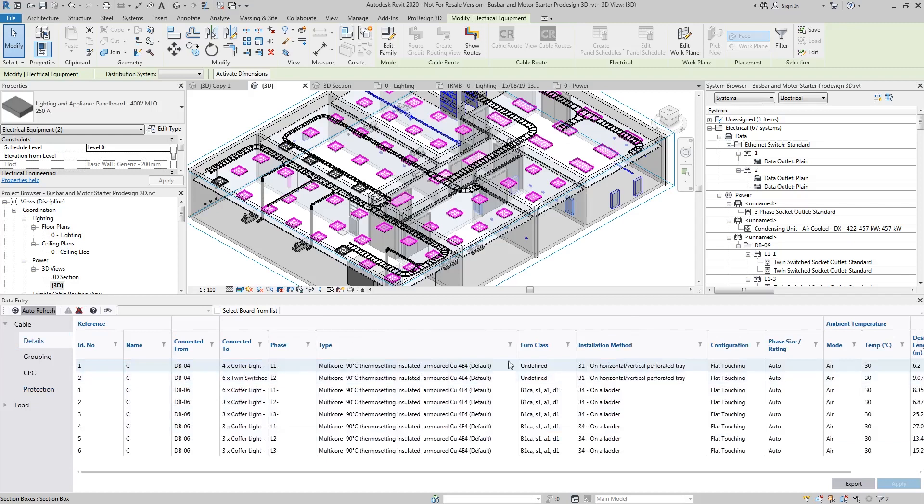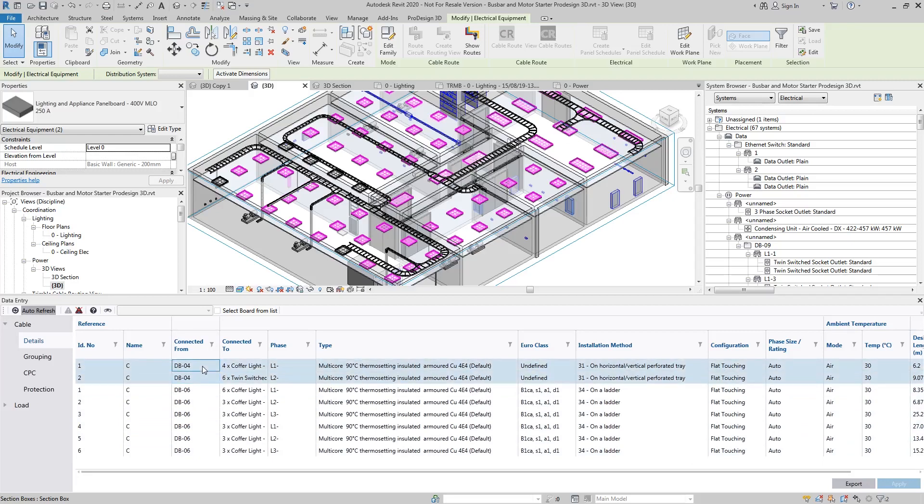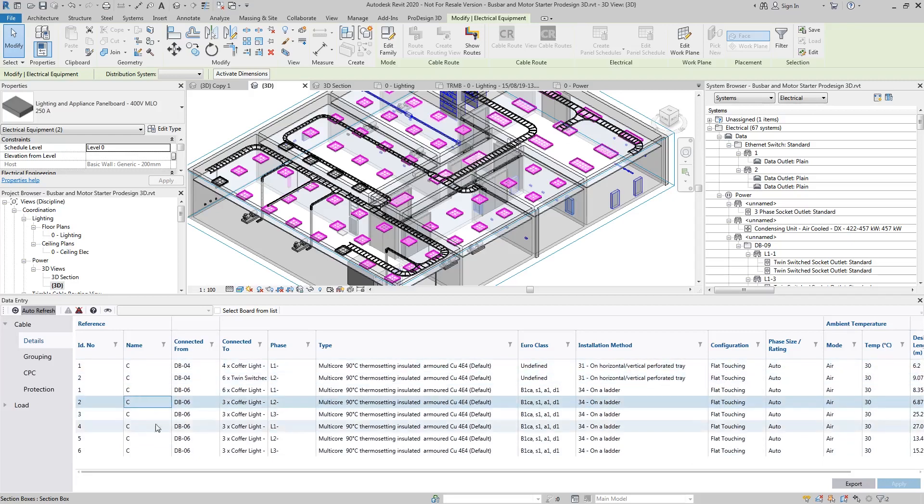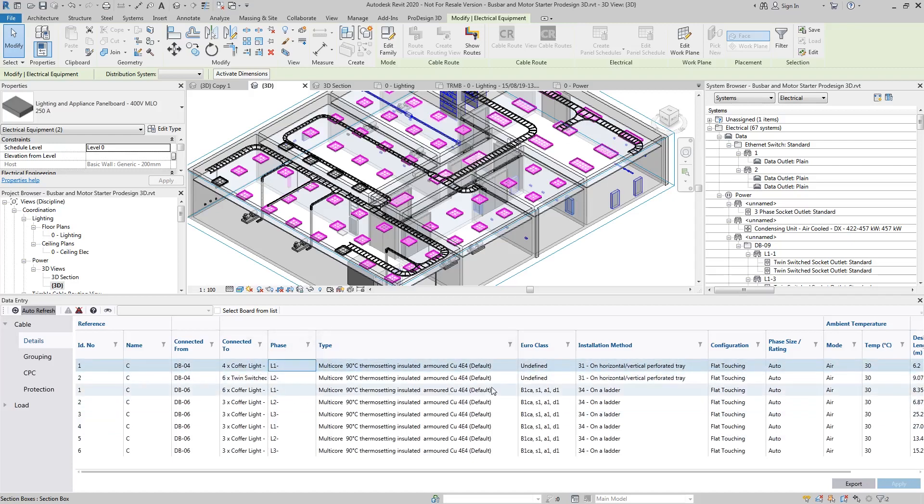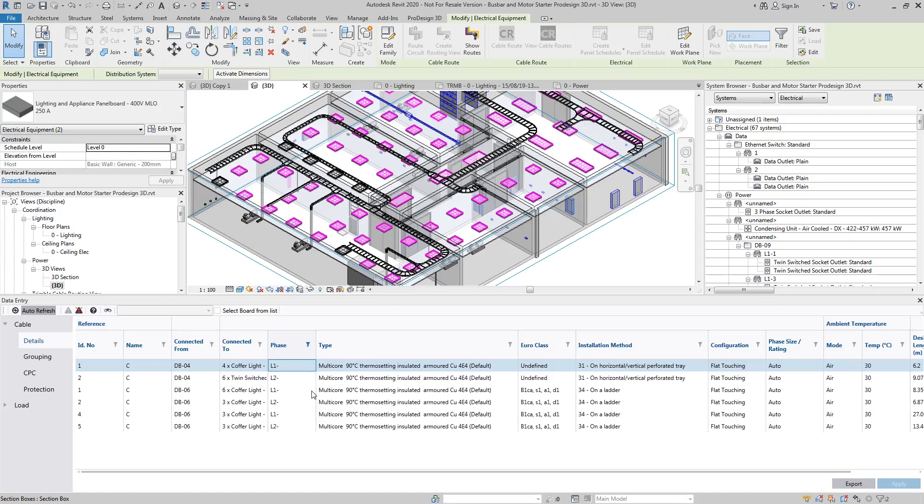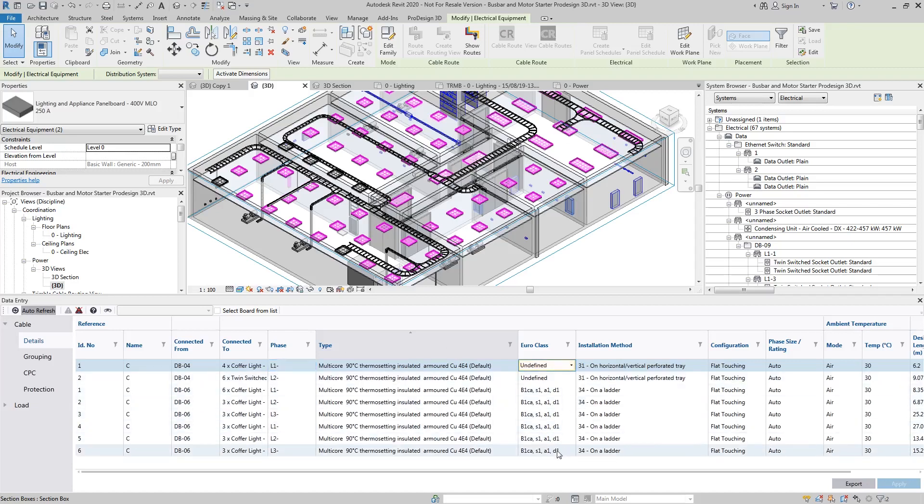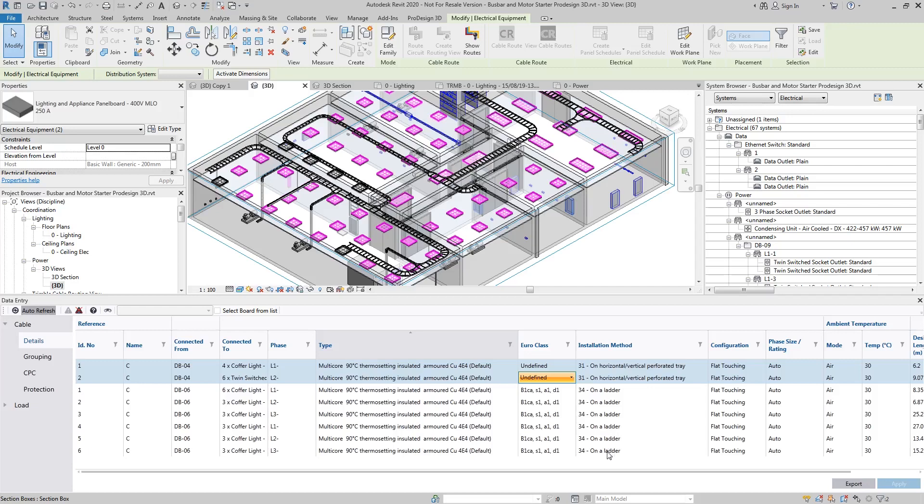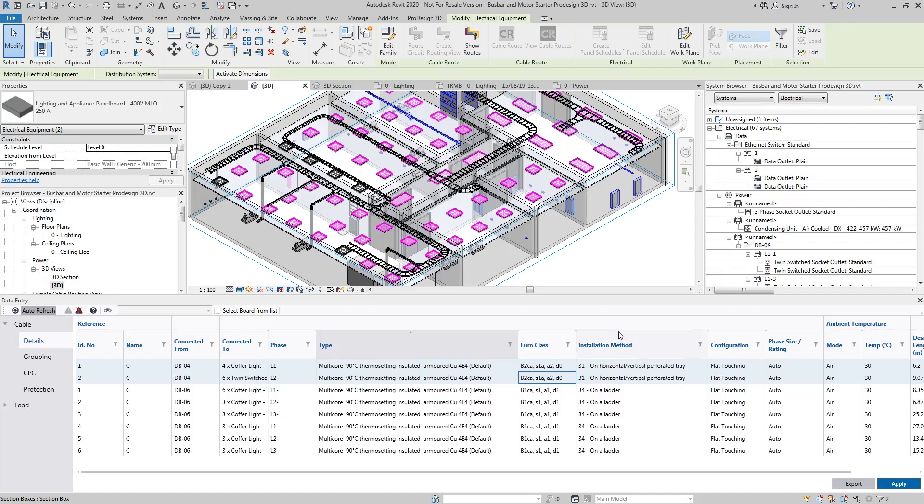We've got the detail side of things as well. This is everything related to the cable. You can make changes to certain parameters—you won't be able to change connected items, you may not be able to change the names and items, but they are there and you can filter those out. If you wanted to filter to only look at certain items, you can do that, or you can clear filters to show you everything. One of the things I might have to do within my project is I've got some cables that I've selected and I've already put the euro class in. Well, these ones are going to be a slightly different euro class. I am just selecting things at random, but we can do that, apply that—it's going to ask me do I want to do multiples—and I can make those changes quite quickly without actually having to go into every dialogue, which is quite useful.